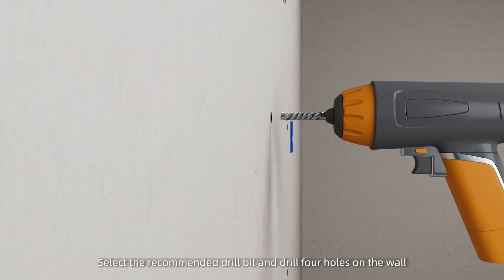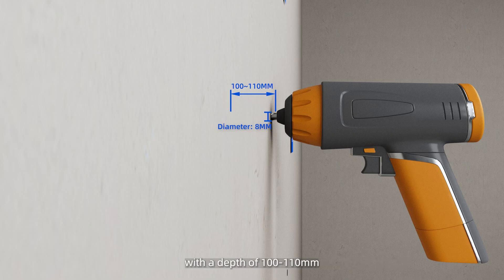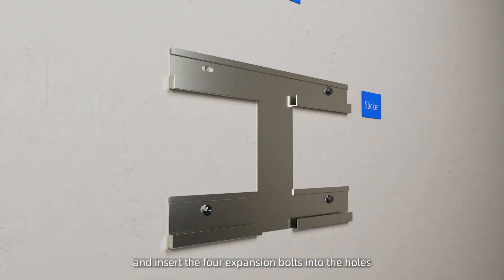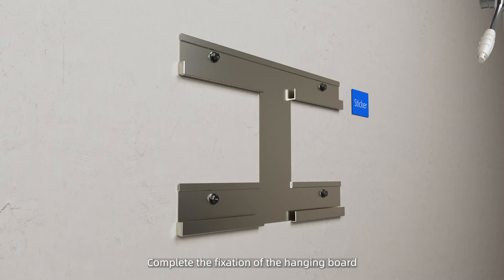Select the recommended drill bit and drill four holes on the wall with a depth of 100 to 110mm. Fix the hanging board to the wall and insert the four expansion bolts into the holes. Complete the fixation of the hanging board.